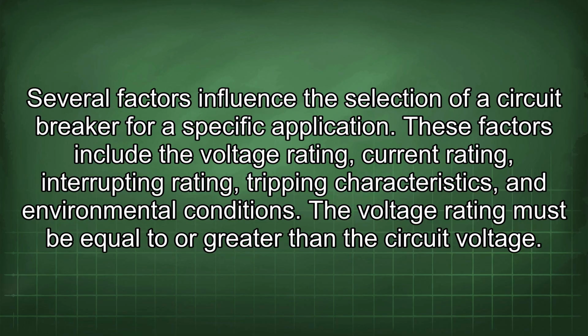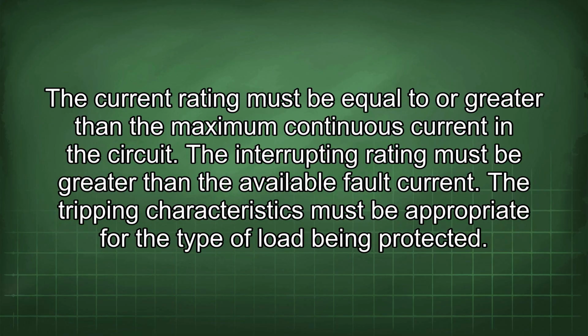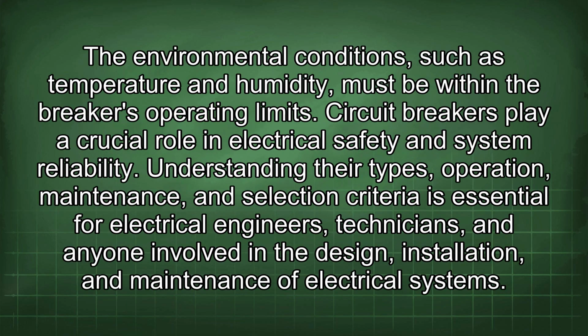Several factors influence the selection of a circuit breaker for a specific application. These factors include the voltage rating, current rating, interrupting rating, tripping characteristics, and environmental conditions. The voltage rating must be equal to or greater than the circuit voltage. The current rating must be equal to or greater than the maximum continuous current in the circuit. The interrupting rating must be greater than the available fault current. The tripping characteristics must be appropriate for the type of load being protected. The environmental conditions, such as temperature and humidity, must be within the breaker's operating limit.